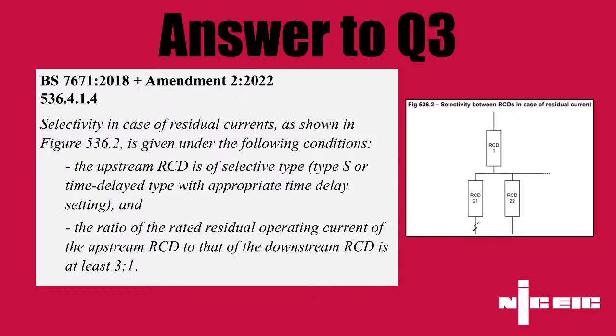536.4.1.4 states that selectivity in the case of residual currents is shown in figures 536.2, and it is given under the following conditions. The upstream device is selective type, so a type S, which is a time delay type with appropriate time delay settings, and the ratio must be 3 to 1. It's to make sure that in the event of a fault on the load side of RCD 21, the upstream device shouldn't operate under fault conditions because it has correct selectivity. The one closest to that fault should operate before the upstream one does.